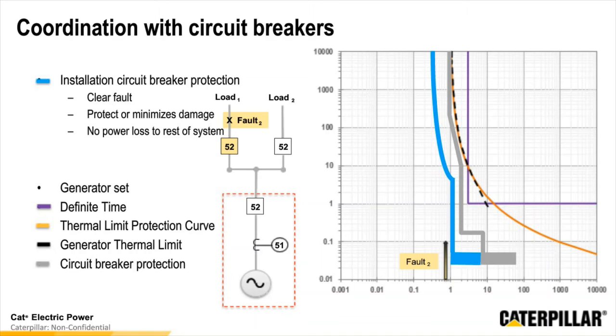So we've worked ourselves outside the generator now. We've completed the relay protectives. We have the generator set protectives, our circuit breaker, and now we're starting to look at the breakers throughout the system. So as we move again more to the left of the curve, we want to continue to add more breakers, more consideration for our loads. So as we think about this now, the breakers are probably going to be something less than 100% of the package at a continuous demand because you're not going to have two loads within a system that are both 100% of the demand of the system.